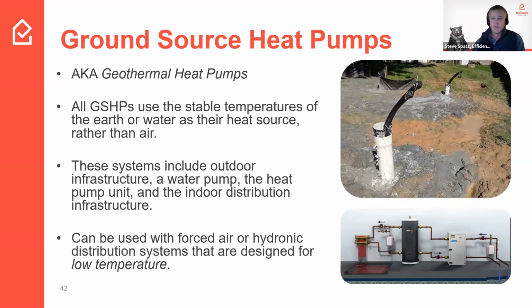The warmer the outdoor air, the more efficient it's going to be and the more heat energy it's going to pull. The colder the air, the less. That being said, any of the cold climate heat pump equipment that we have rebates available for and that are a part of the programs that we promote is equipment that works still very effectively at temperatures below zero outdoor temperature. Now, that being said, a ground source system is going to offer more consistent temperatures throughout the year. It's going to offer more consistent levels of efficiency for operating the system, but it's also more infrastructure, significantly more infrastructure involved in putting one of these systems in.